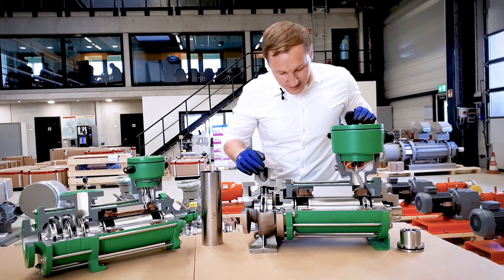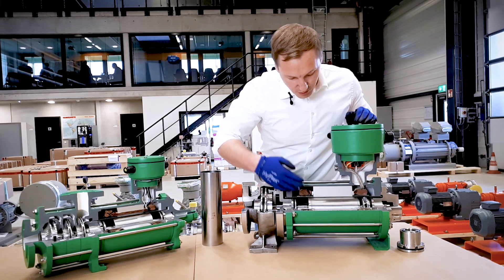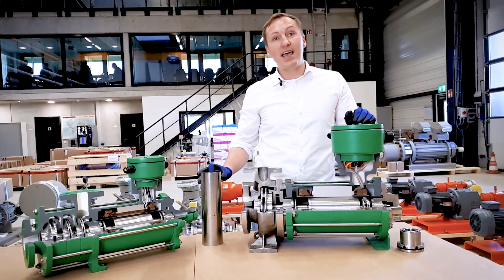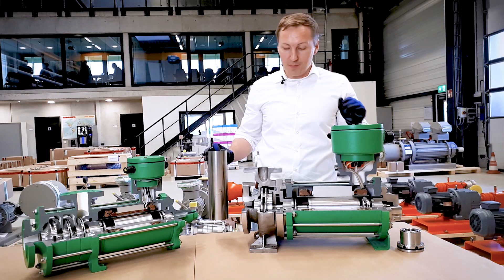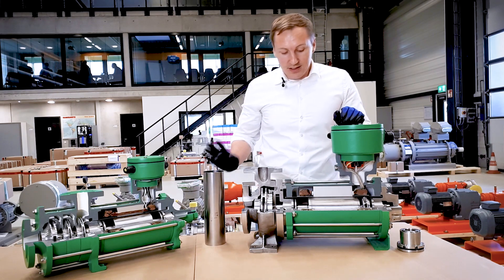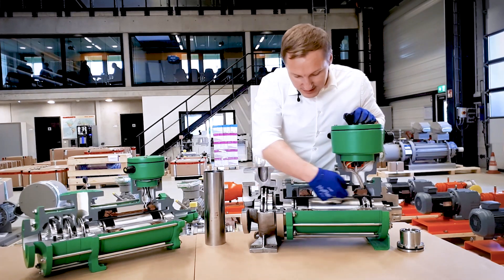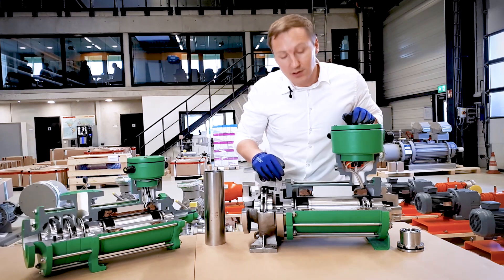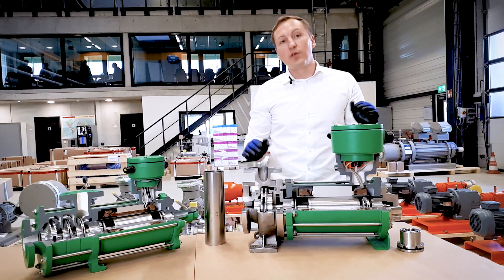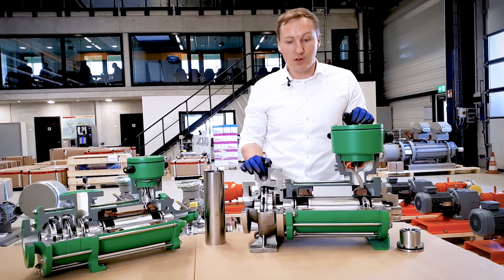Second, we have a rotary part of the motor which is the rotor, and a stationary part which is the stator, and they are divided by a can. That is why this pump technology is called a Canned Motor Pump. This is the can. So we have two safety containments. The first safety containment is inside the can, and the second safety containment is the housing of the pump. This means if you are looking for a very safe technology, then the Canned Motor Pump is the right choice for you.